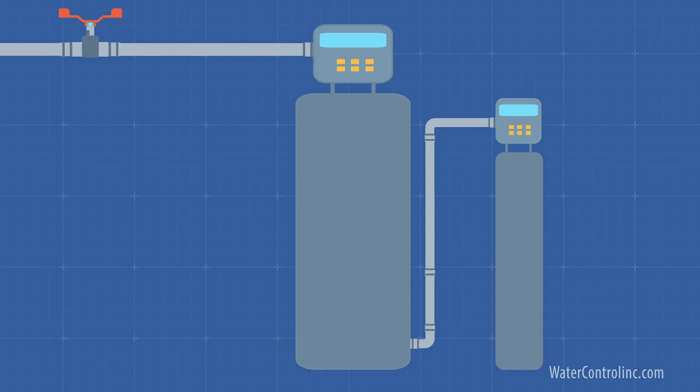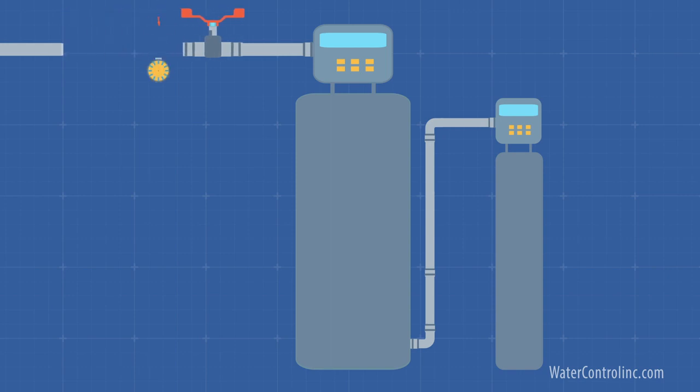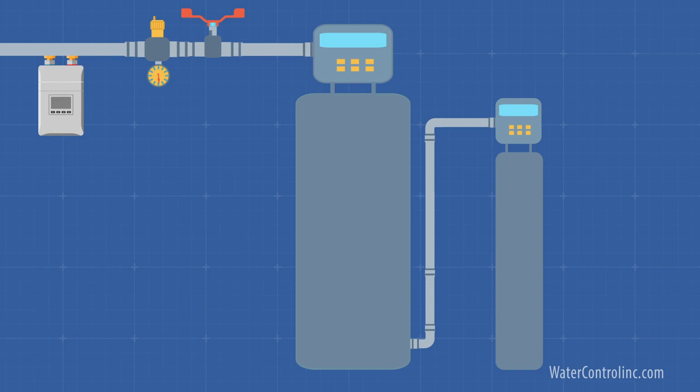It's also possible to deal with pH issues via the injection of certain chemicals, such as acetic acid or soda ash solution, or others. These systems involve simple chemical injector pumps which treat the water as it enters the facility.